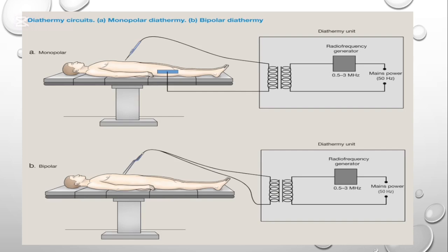This image shows the difference between monopolar and bipolar diathermy. In monopolar diathermy, the electric current flows from the tool through the patient's body and exits through a metal plate placed on the skin. It is useful for treating larger areas. In bipolar diathermy, the current passes between the two tips of a special tool, so it does not go through the whole body. This method is safer and better for small or delicate areas.